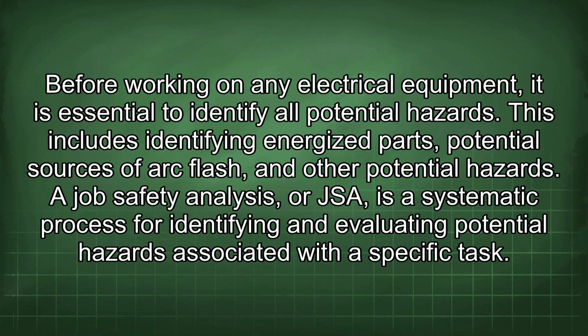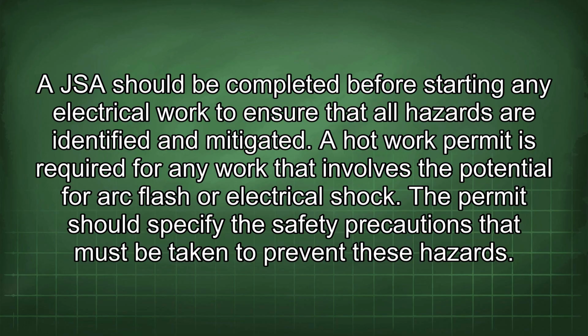Before working on any electrical equipment, it is essential to identify all potential hazards. This includes identifying energized parts, potential sources of arc flash, and other potential hazards. A job safety analysis, or JSA, is a systematic process for identifying and evaluating potential hazards associated with a specific task. A JSA should be completed before starting any electrical work to ensure that all hazards are identified and mitigated. A hot work permit is required for any work that involves the potential for arc flash or electrical shock. The permit should specify the safety precautions that must be taken to prevent these hazards.